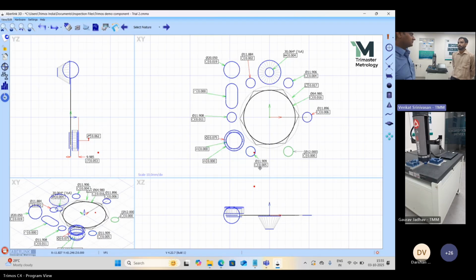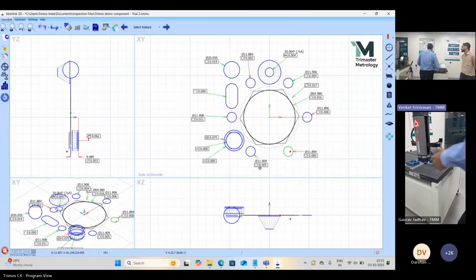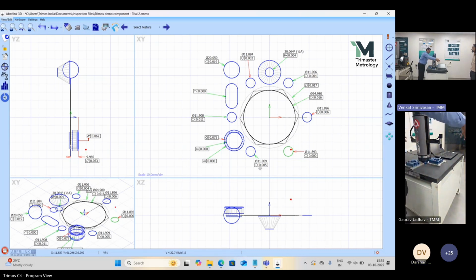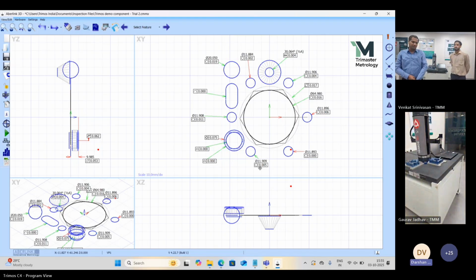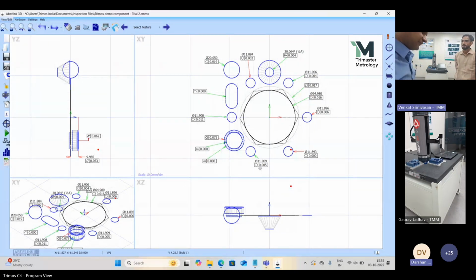That is right, up to about 200 millimeter diameter you can measure using this. And we can also put the machine in the center and measure, for very large rings. You can actually set the machine in the middle of the bearing and have it go all around, with the part surrounding the machine. Definitely, that is also possible. So what we were assuming was that only outside we can put the part and measure - that was our doubt. Now you have cleared it, that we can put the part surrounding the machine itself.